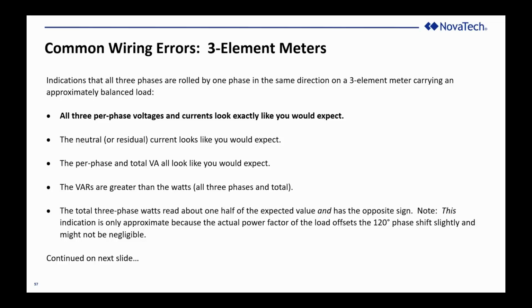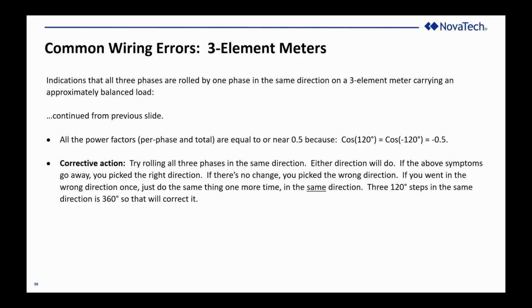Oh, and you want to take into consideration that if you have a non-unity power factor, 120 degrees may be a power factor of 0.5, but for 125 degrees or 115 degrees, you incorporate the phase angle of the actual power factor into that 120 degree shift, and it may not be exactly half. So what you're looking for is about half here. What else would you see? All the power factors are going to be equal to about half.